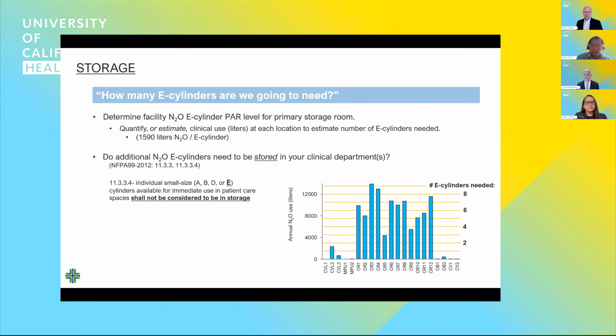You can see in the figure on the lower right there, that's looking at annual consumption by clinical location in one of our Providence hospitals. And you can see, in OR3 there in the middle, we project that they were going to need 9 e-cylinders of nitrous for a year, whereas in OR5, they're only going to need 3. When we first did this assessment, we were all kind of biting our nails, hoping that this would bear out and be accurate. Having done this now at 50 plus hospitals, I can tell you that this is quite robust and valid.